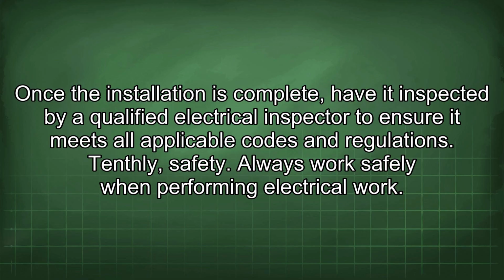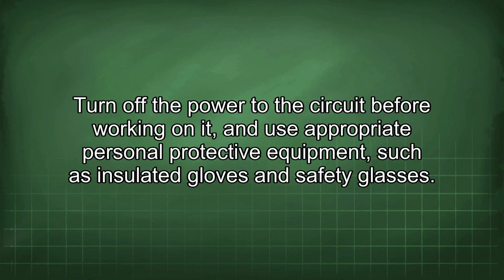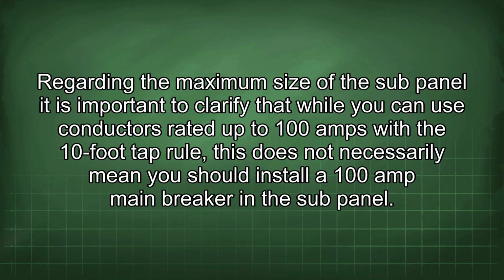Always work safely when performing electrical work. Turn off the power to the circuit before working on it, and use appropriate personal protective equipment such as insulated gloves and safety glasses. Regarding the maximum size of the sub-panel, it is important to clarify that while you can use conductors rated up to 100 amps with the 10-foot tap rule, this does not necessarily mean you should install a 100 amp main breaker in the sub-panel.